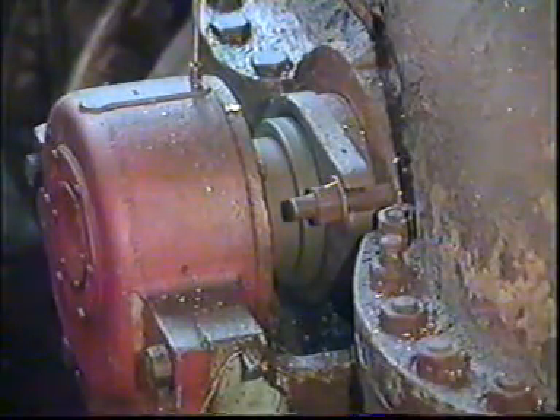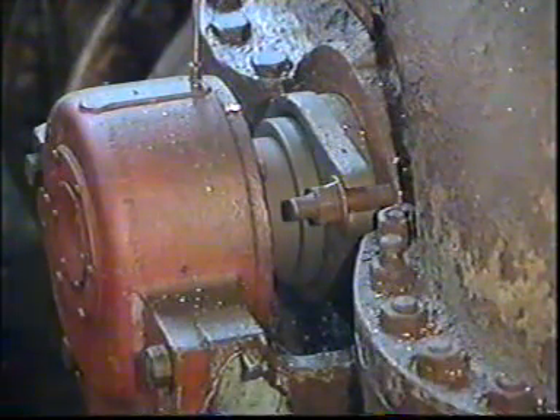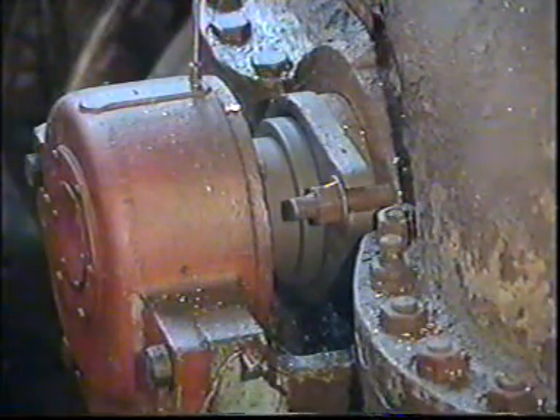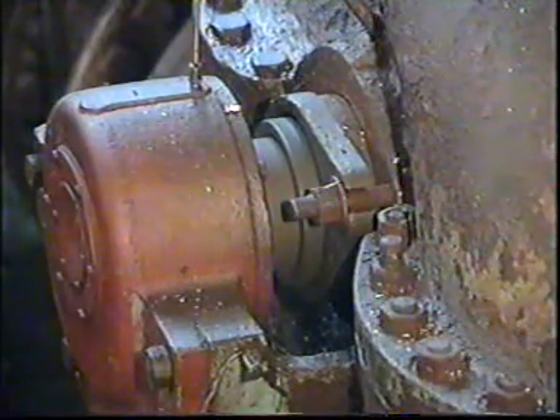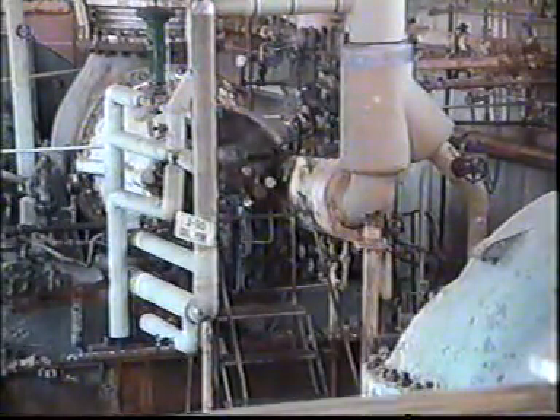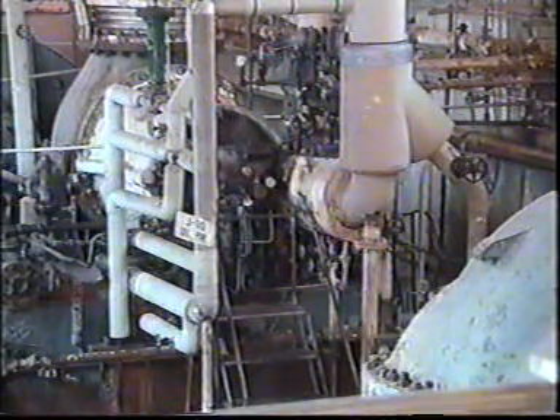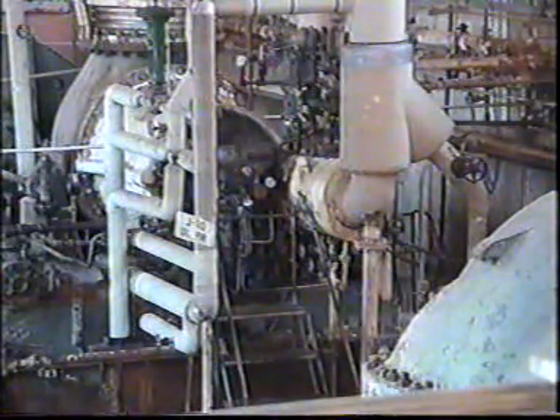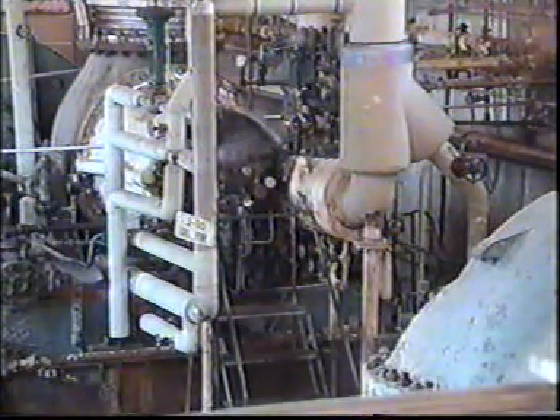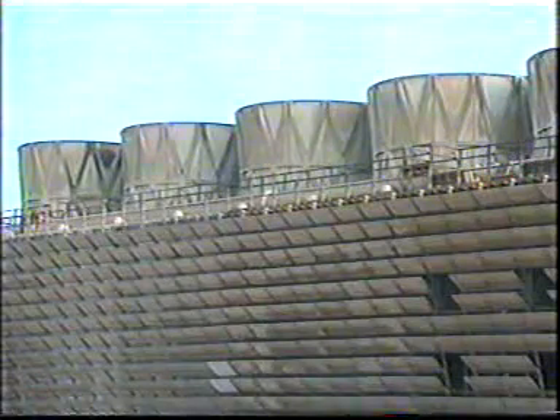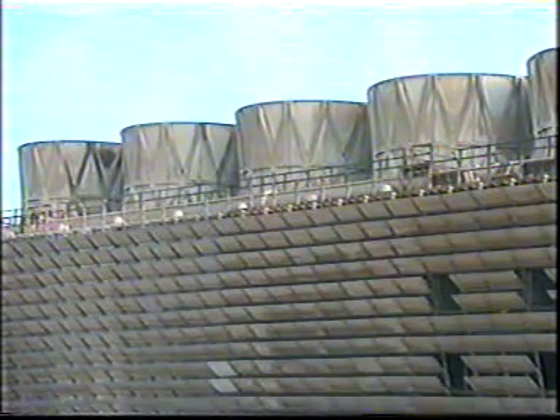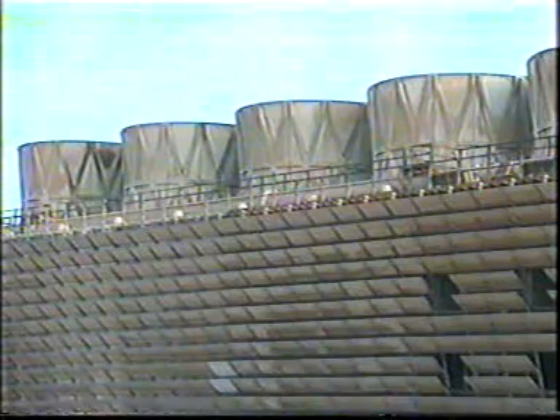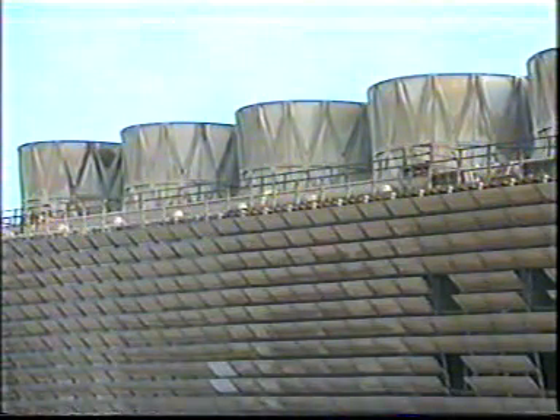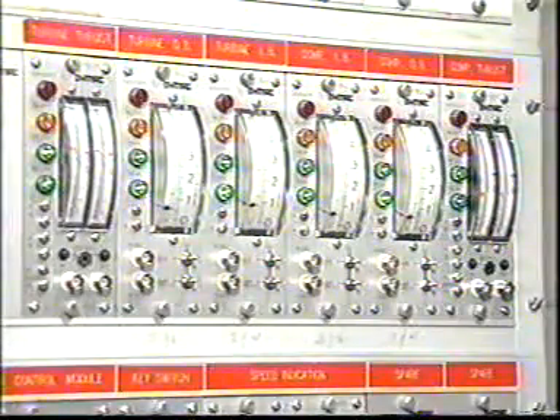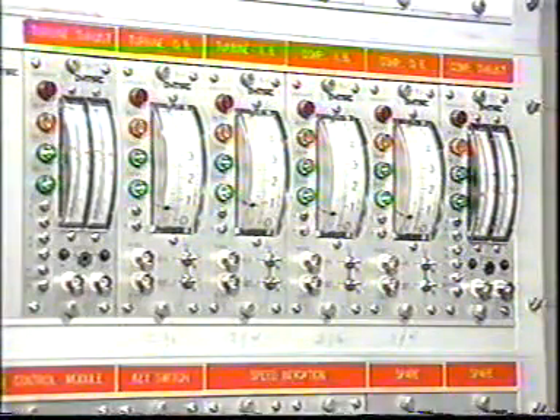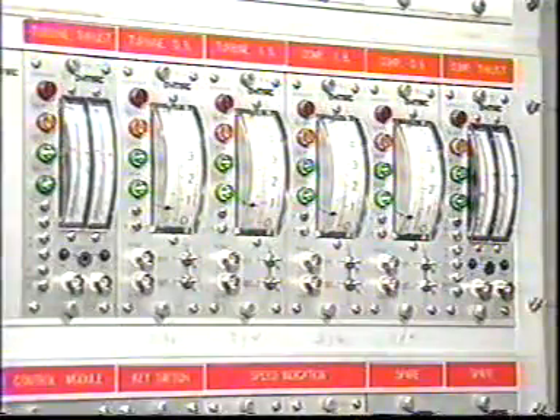Critical machines, machines where problems could develop rapidly, or machines whose failure could result in hazards to personnel, should have continuous monitoring. For example, a turbine typically spins at very high speeds. If a problem were to develop and the indications were to go unnoticed, a catastrophic problem could develop very quickly. A cooling tower fan usually has very large blades. If the fan threw a blade, the resulting imbalance would destroy the assembly. Continuous monitoring provides for early detection and protective action for serious vibration problems.